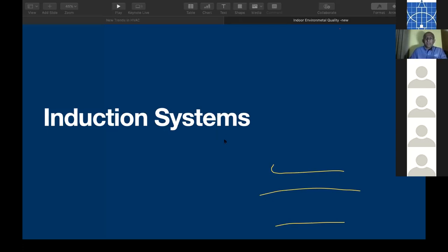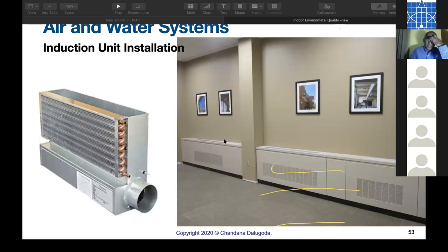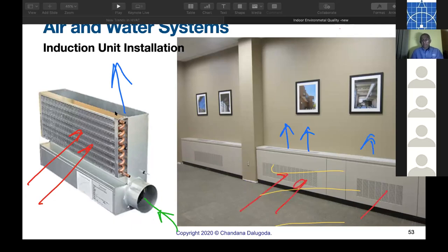Next is induction system. Induction system, this is going back to all water that we discussed, rather air and water systems. This is the induction unit. Inside this, primary air comes here, secondary water comes here. Induction happens through this grill. And cold air comes out. Primary air coming this way. So cold air comes this way. Room air induced, but maximum installation is 120 watt per square meter load. That's the only constraint.